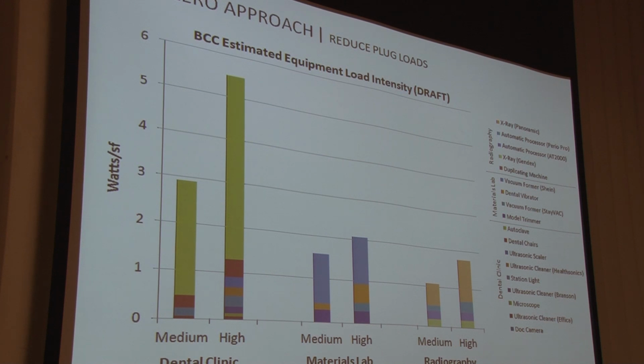They run actually for a while each, and they might have 6 on at a time, which was the case when we walked into the room. You can go over there and you feel the heat coming off of these things. So either putting them in a separate room or using the return air locally in that spot to actually pull some of that heat out of the space before the fan coil units have to cool it all down. So we're looking at not just right sizing, but also looking for design opportunities by understanding the equipment and the program for the building.